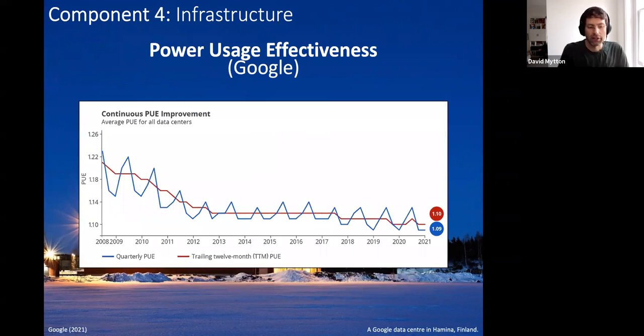However, the large hyperscalers are pushing these limits, and Google is one of the few, or the only one of the three, that publishes its PUE values for the facilities it owns on a quarterly basis. You can see they've been pushing down not just the quarterly PUE, which changes with season and location, but also their trailing 12-month average across their entire fleet, getting down to about 1.09, 1.10, which is close to the limit you can reach.